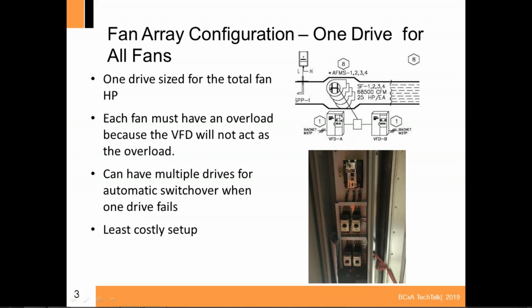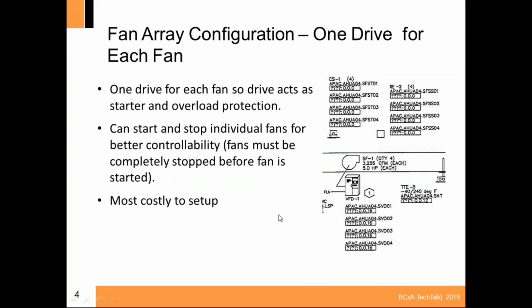So the drive, in effect, isn't going to act as an overload limiting device. In other words, if only 2 fans are running at a time, the drive is set to trip out at the horsepower of, say, the 100 horsepower and not the 50 horsepower. So the drive will not protect those motors if they start to overload. It's a natural thing.